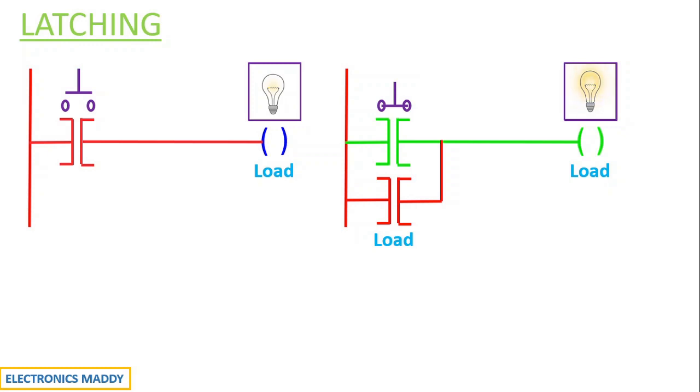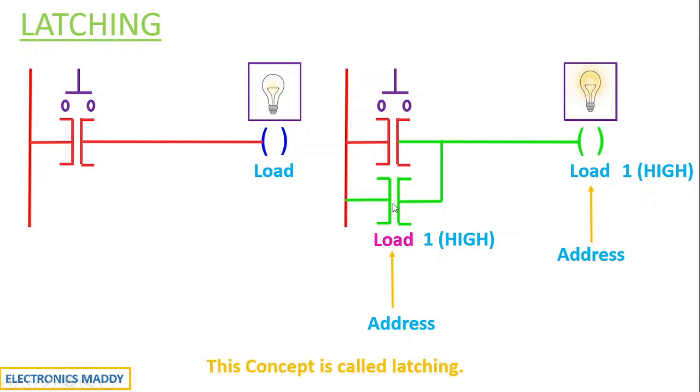What happens internally is since the address corresponding to the load becomes equal to one - that is high because the light is glowing - the same address is used here as well, so this contact also gets energized. Now if I release the push button switch, even if this contact becomes equal to open circuit, the current will still be flowing through this path. This concept is called latching.